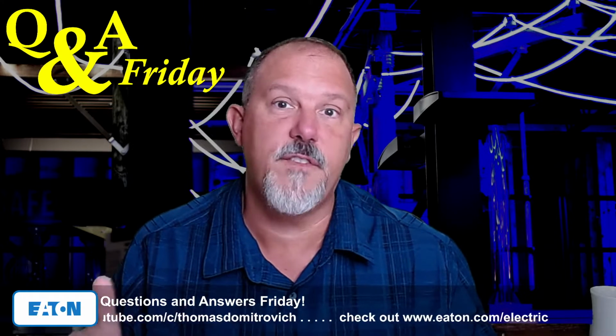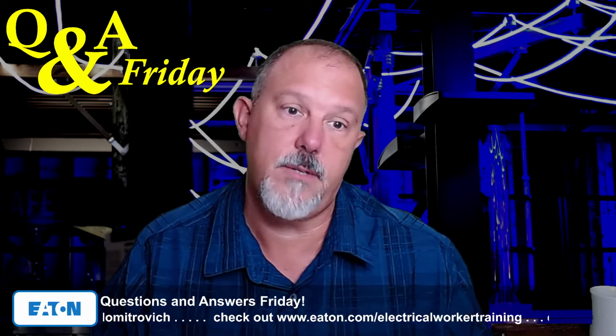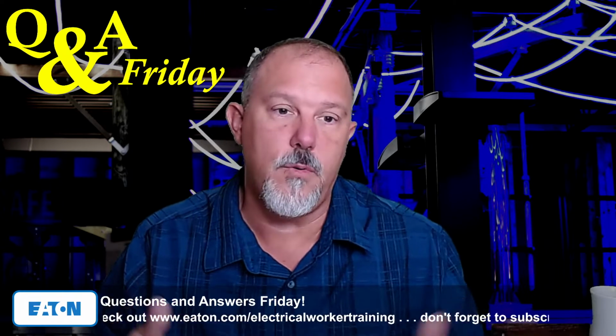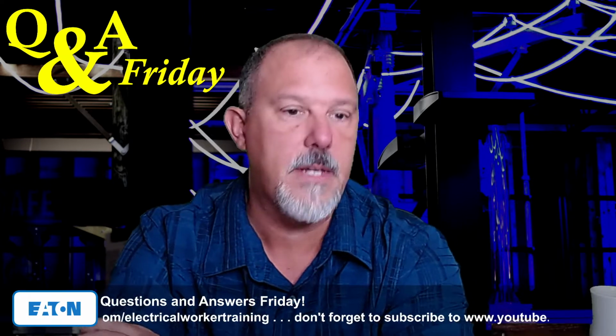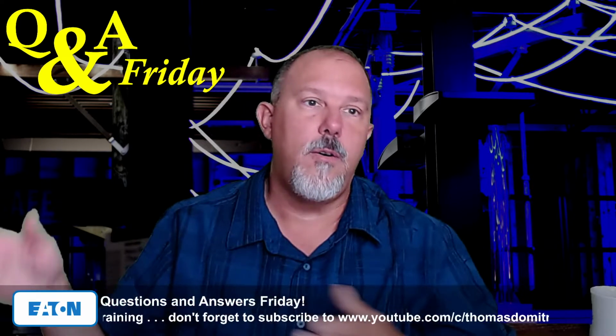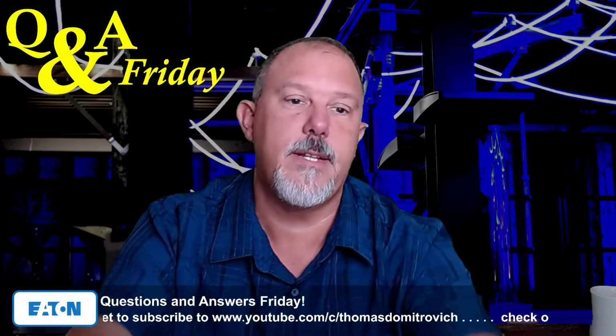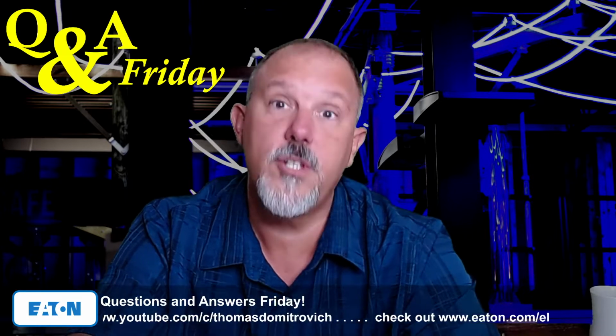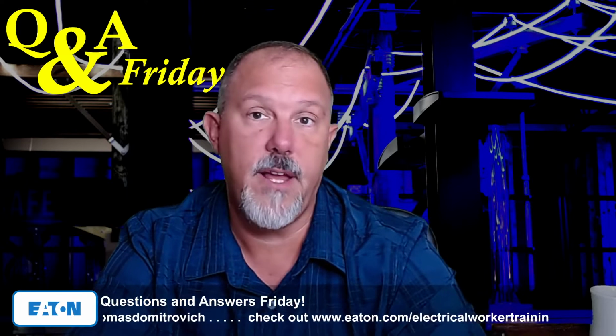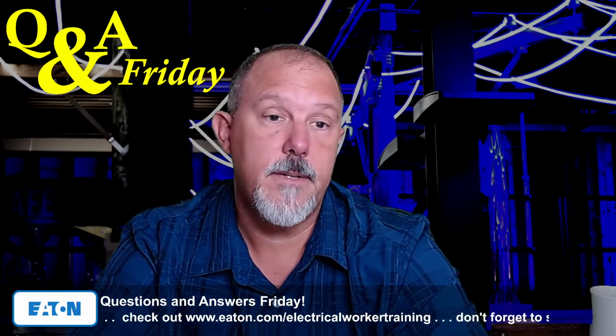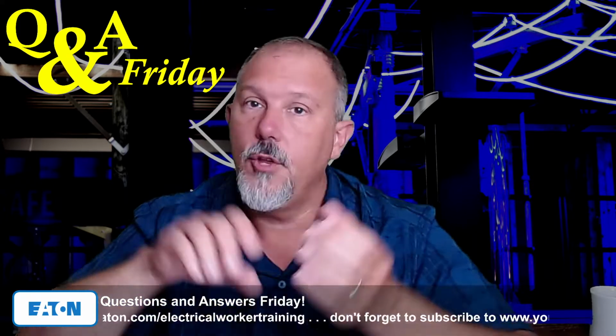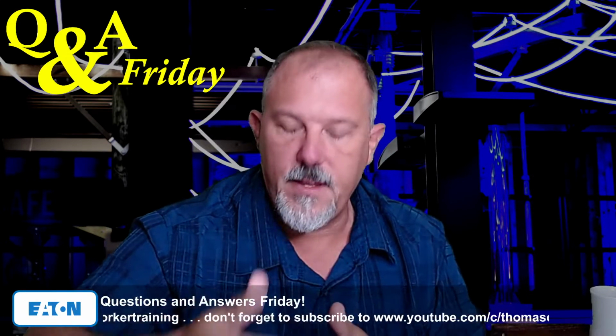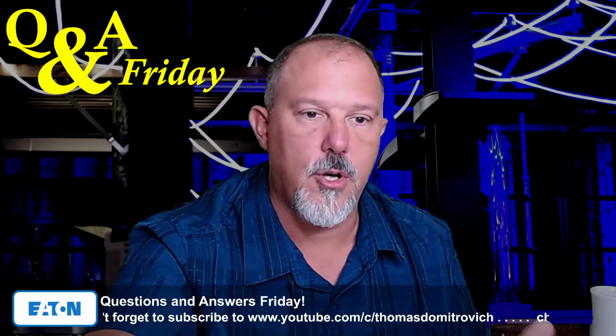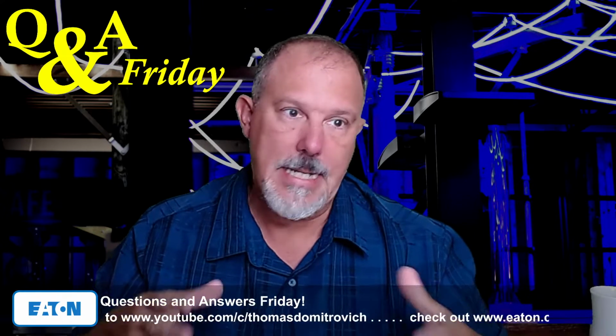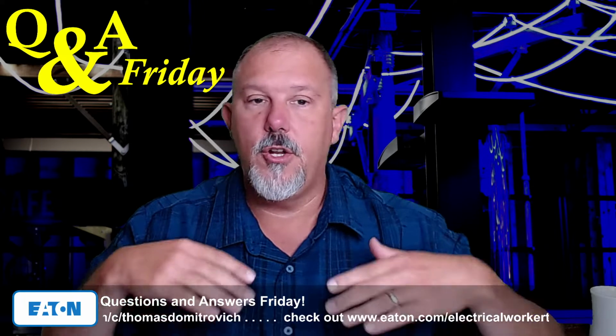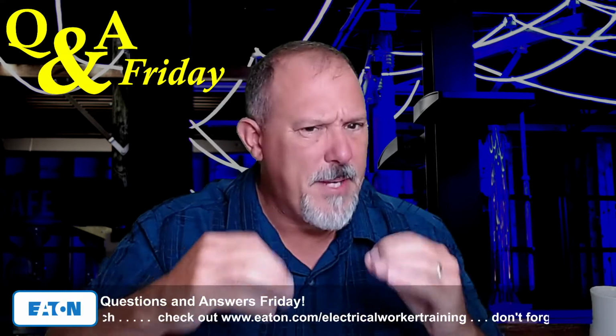In fact, we found some lower efficiency units that are using the equipment grounding conductor as a current path. So you've got to be careful using the words most and all. I'm not going to say all, I'm going to say we found some installations, some solutions, that are intentionally using the equipment grounding conductor for a 120 volt type of application within that unit because they don't have a neutral there. And again, that's a 60 hertz thing. You can say you won't have a problem if you just would have, but that violates Article 250. Article 250 on grounding and bonding tells us you can't have objectionable currents on the equipment grounding conductor. So objectionable currents need to be looked for regardless of the application. And we have a body count associated with it. So you've got to be careful there.